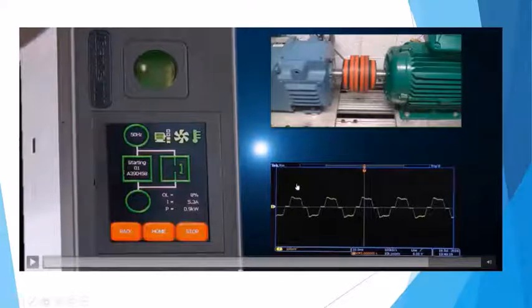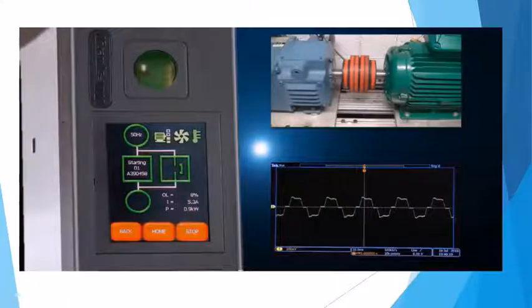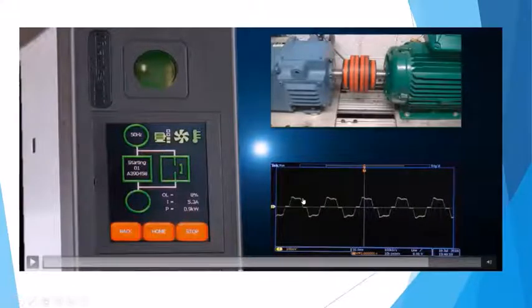The issue is that you have to size the soft starter or the thyristor device to be able to handle that continuous current, not just a set of inrush startups. So some of the industry has gotten to where they've provided a little bit weaker soft starter to get by, to compete with competition. But at the end of the day, you want heavy thyristors in there that can actually handle that current continuously, because this can give you as much as an extra 10 or 15% on your pump of how much total power it is, especially if you're regulating and throttling the valve or the output.